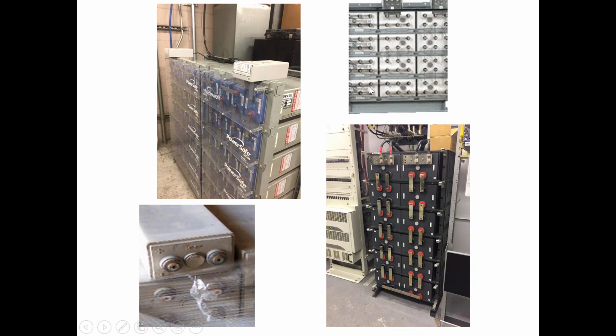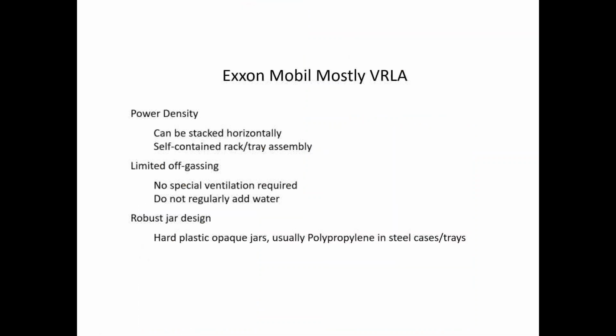These batteries are typically installed horizontally. That's the idea. It gets you higher floor loading, but it gets you power density because you can stack these guys up pretty tall, as opposed to along a battery rack. And again, power density and footprint are much more advantageous. This lower corner is a picture of just a cell. So the cell has been unloaded from the steel tray. And it's interesting, I have a picture later in the presentation of the back of one of these. So just keep in mind what this thing looks like, and I'll reference that battery a little bit later.